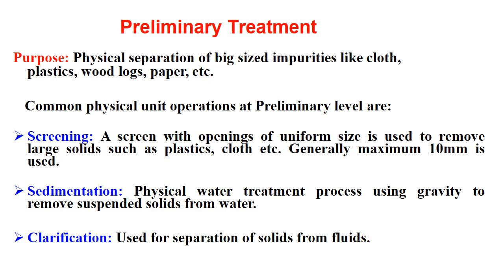The common physical unit operations at the preliminary level are screening — a screen with openings of uniform size to remove large solids such as plastics and cloth, generally a maximum of 10 mm. Then sedimentation, a physical water treatment process using gravity to remove suspended solids, and clarification used for separation of solids from fluids.